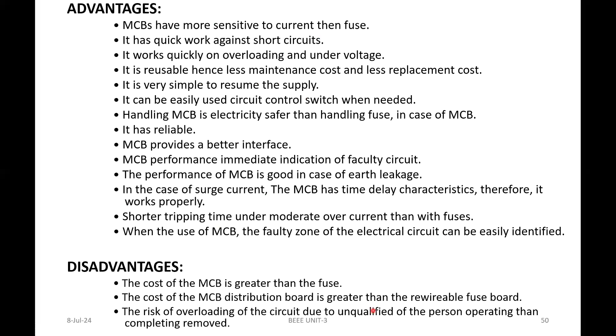From the disadvantage point of view, the cost of an MCB is somewhat higher than a fuse. The cost of an MCB distribution board is greater than the rewirable fuse board. The risk of overloading of the circuit due to unqualified personnel cannot be ignored, because there is some logic behind MCBs. These are the advantages and disadvantages, or merits and demerits.